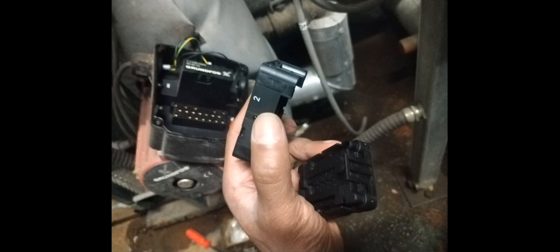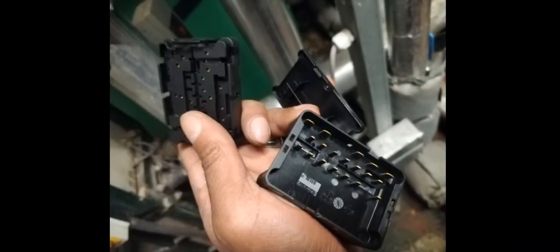And this is how you have to turn off the power and do safe isolation. And then you can remove the cartridge and then flip it around. You disconnect it and then flip it around, as you see here. And then you get speed 1. And then here's me checking the power with speed 1, how many amps it's drawing.